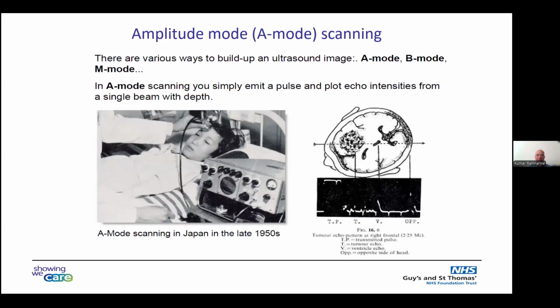And the first ultrasound devices are called A-mode devices, amplitude mode. So an ultrasound scanner, a transducer, can be made to emit an ultrasound pulse using the piezoelectric effect. So the piezoelectric effect means that certain materials, when subjected to a voltage, a displacement, will vibrate, and that generates the ultrasound. But also, the reflected ultrasound signals are detected by the piezoelectric crystal and converted into a voltage signal. So this is the piezoelectric effect. It allows the crystal to act as a transmitter of ultrasound and also as a receiver to detect the signals that are reflected back from different interfaces.